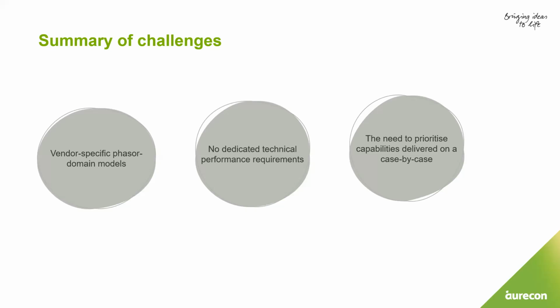The first one was the lack or immaturity of the phasor domain models. This might look counterintuitive, since typically people think EMT models are the harder ones, but EMT models these days are essentially a one-to-one representation of the source code — we really don't need to do much. Whereas the positive sequence, or any sequence phasor domain model, needs to be developed by humans, and these models are not mature at all. I can only tell you one, two, or three suppliers had good enough phasor domain models for grid forming batteries.